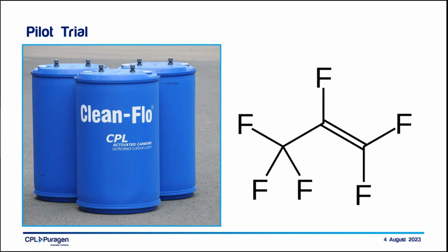An interesting thing that was observed during the trial is that the activated carbon was reducing the COD level coming from the existing biological treatment works below the required emissions limit. And so with that additional information, the client decided not to carry out the upgrades to the biological treatment system, because that was going to be extremely costly for them. So they didn't need to do that, and they were very pleased.